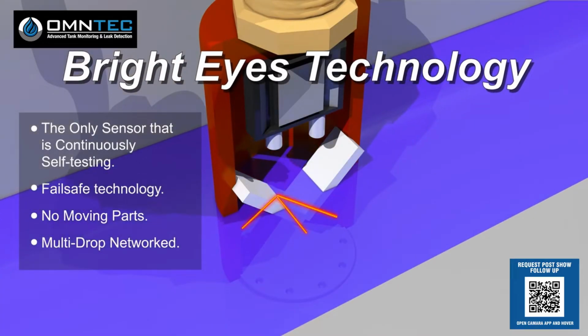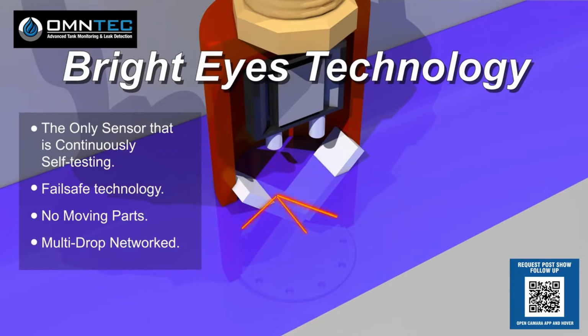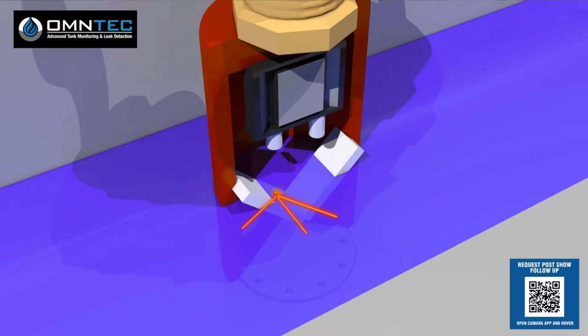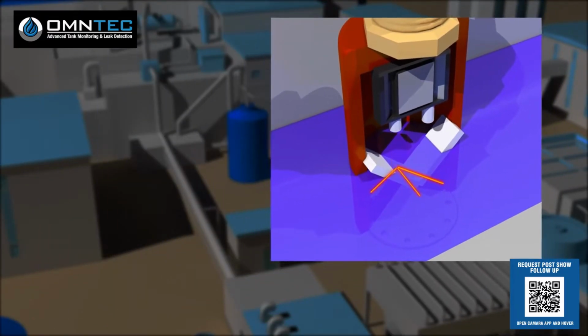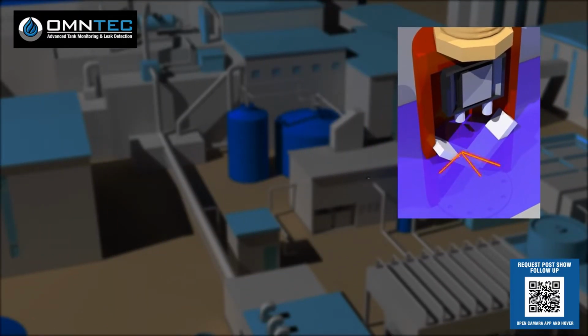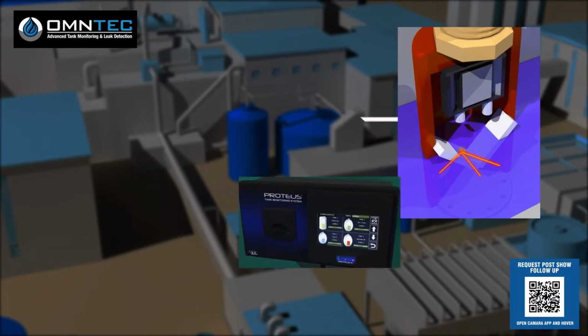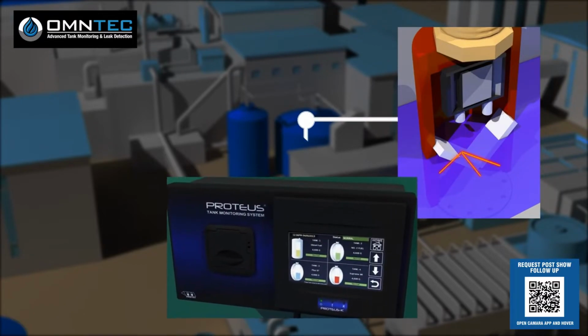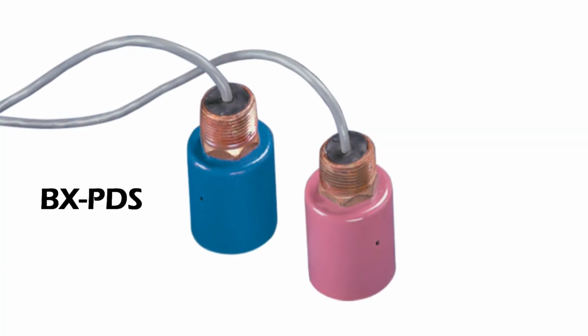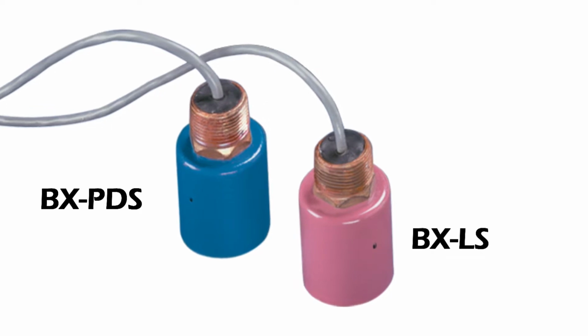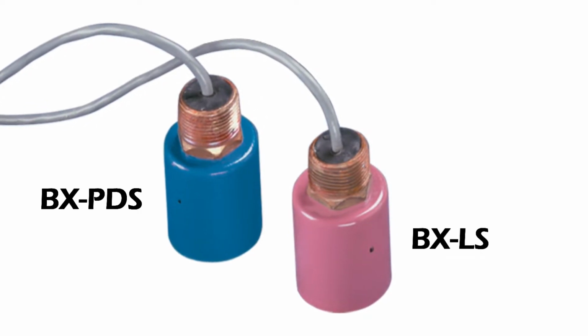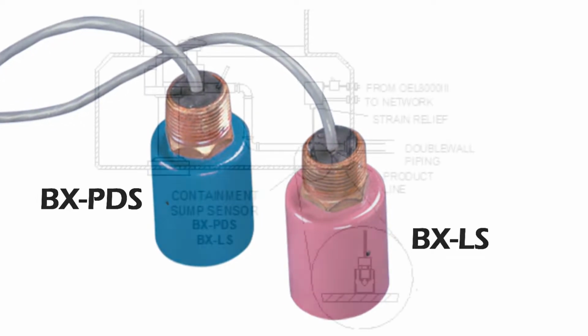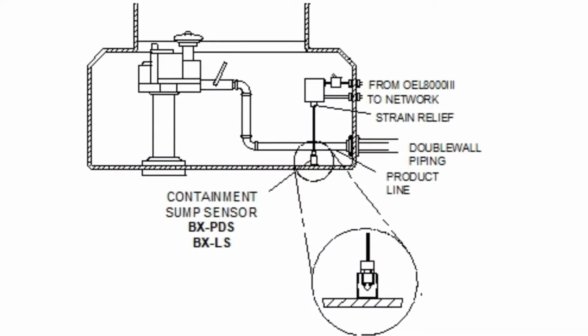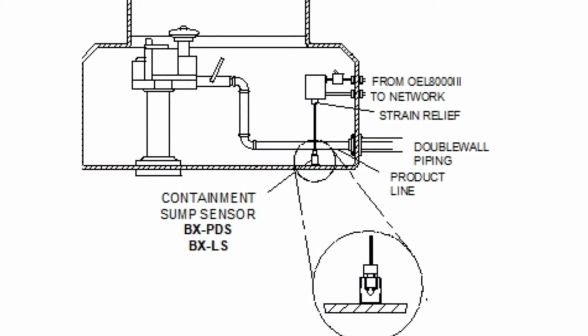Under a wet condition, the light from the LED is refracted away from the LED detector. The signal produced by the microprocessor sends an alarm condition to the controller. A conductivity electrode in a product distinguishing sensor determines if the liquid has conductivity and reports this as a water condition. The BXPDS and BXLS are general-purpose sensors designed to accommodate a variety of applications. They are ideal for sumps, dispensers, and containment areas.